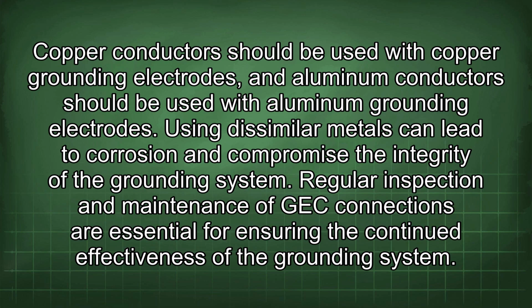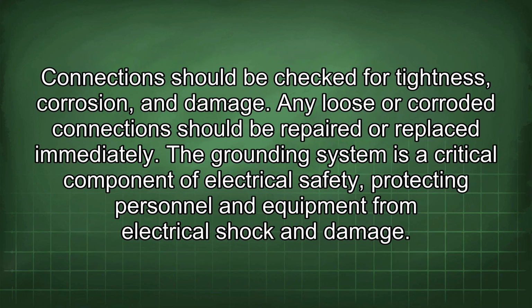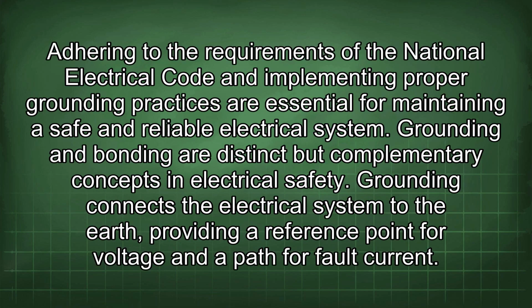Regular inspection and maintenance of GEC connections are essential for ensuring the continued effectiveness of the grounding system. Connections should be checked for tightness, corrosion, and damage. Any loose or corroded connections should be repaired or replaced immediately. The grounding system is a critical component of electrical safety, protecting personnel and equipment from electrical shock and damage.